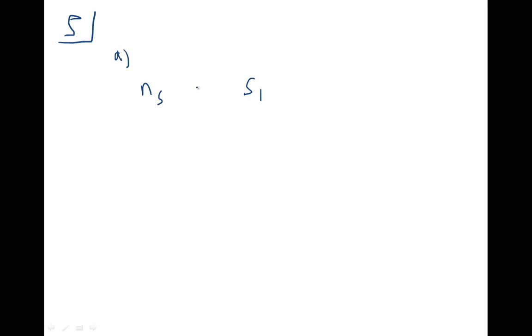Once you have slip, you can use the fact that torque developed 1 over torque developed 2 has to be equal to S1 over S2. You can use this to find your new slip because you have your new torque: 20 Newton meters from before, and now 34 Newton meters. From those values, you can find your S2.